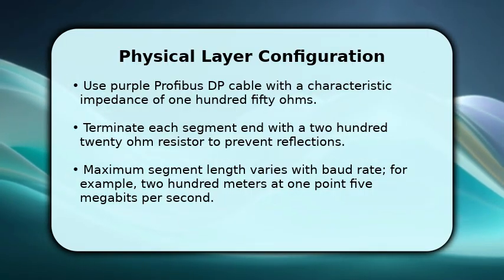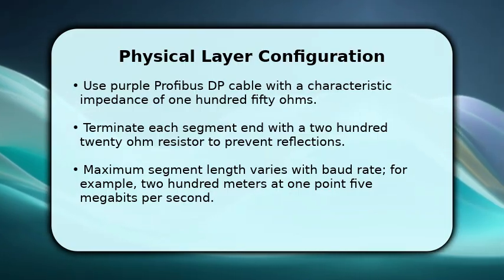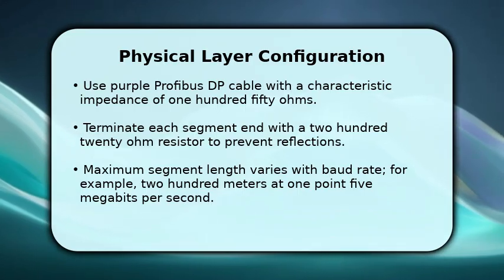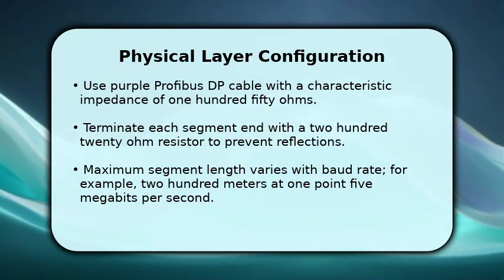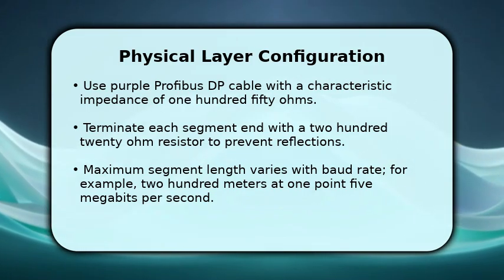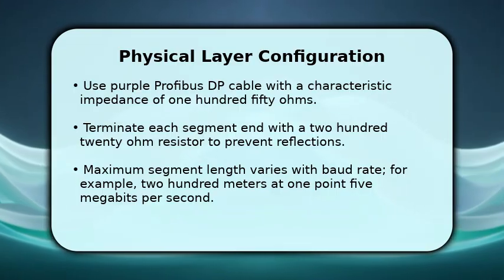Remember that maximum segment length depends on your chosen baud rate. For instance, at 1.5 megabits per second, the limit is 200 meters. Also, ensure adequate separation from power cables to minimize electromagnetic interference.